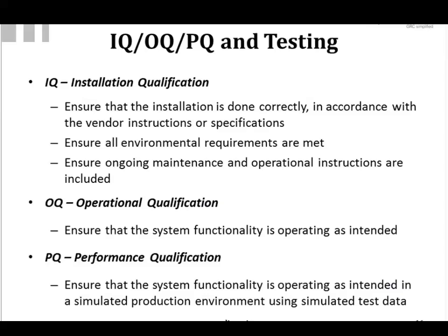If you have requirements listed that are not things you're going to do or use in your environment, don't include them because the FDA will expect you to test them. So leave them out of your requirements, but you can have them noted somewhere just so that you know you can turn those features on if you, at some time in the future, need to add them. But of course, if you add them, you'll have to do some testing.